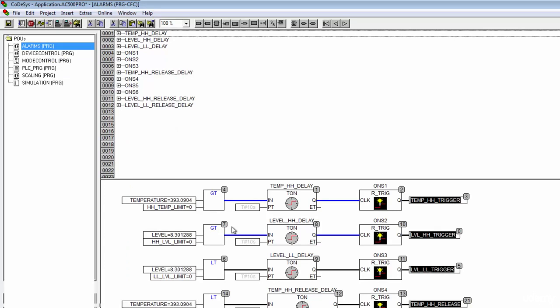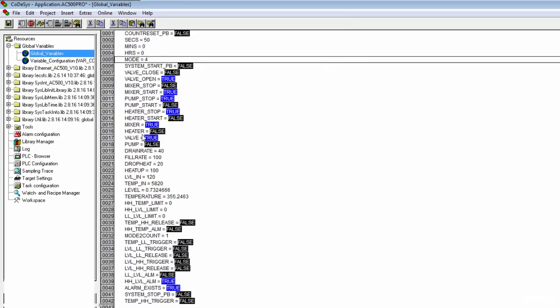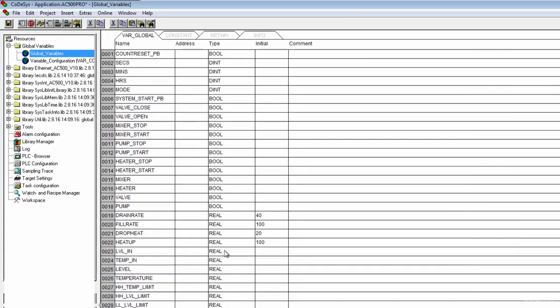Now that I've redefined all of these things as globals, what happened is we actually retained some different values when I restarted. Let's fire up and see what happens — mixer running, heater running, temperature looks good, level coming up, and we've already jumped to mode 4 again with a high-high level alarm. Let's go into our alarms and check the level limit. We've got our high-high limit set at zero — good news is alarms are working, bad news is I didn't have the limit values plugged in. Let's stop, go offline, and set: high-high temp limit = 600, high-high level = 90, low-low level = 10.